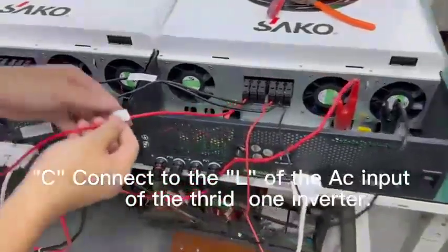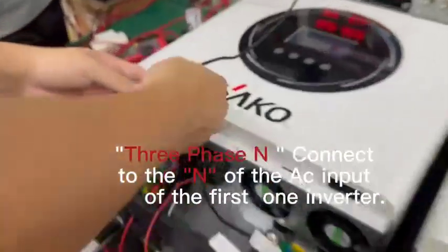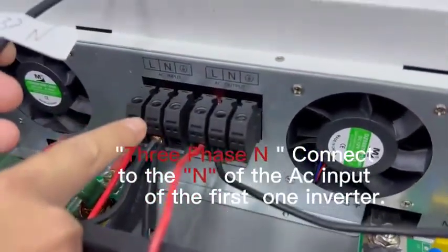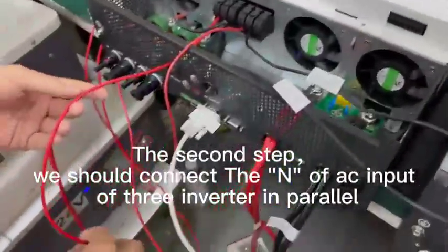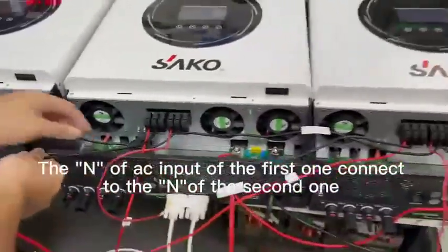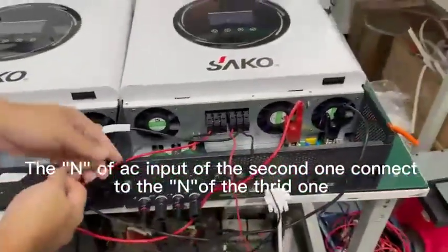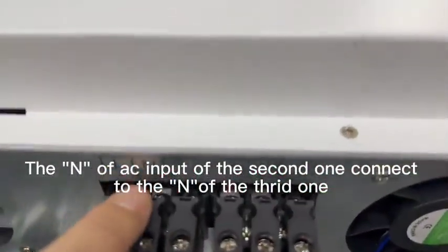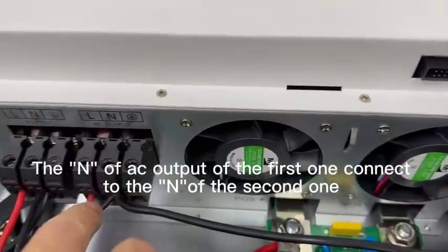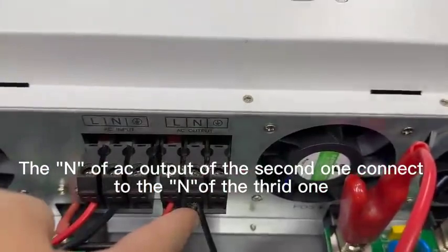Connect phase C to the AC input L of the third inverter. The neutral wire from the three-phase supply connects to the AC input N of the first inverter. Then connect the AC input N in parallel: the first unit N to the second unit N, the second unit N to the third unit N. Also connect the AC output N of the second unit to the AC output N of the third unit.